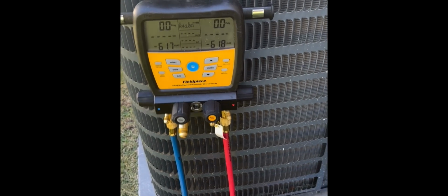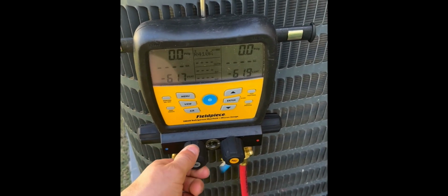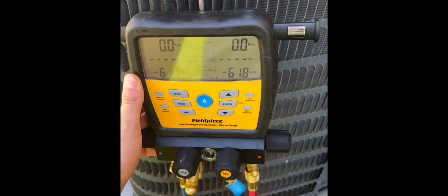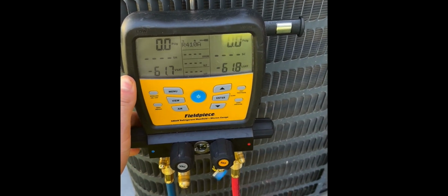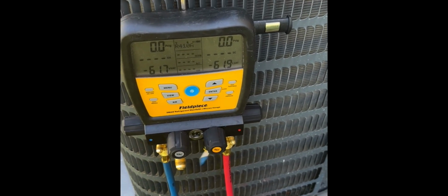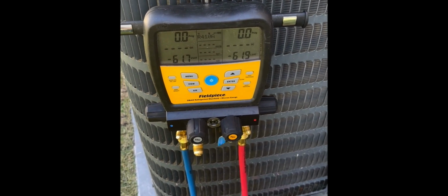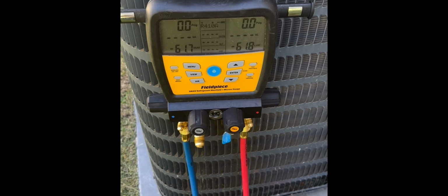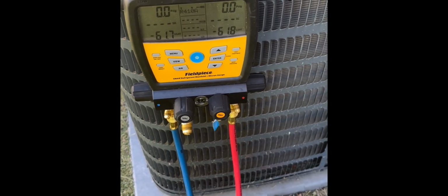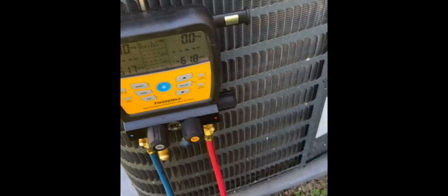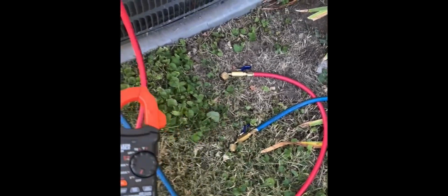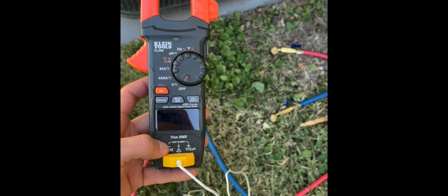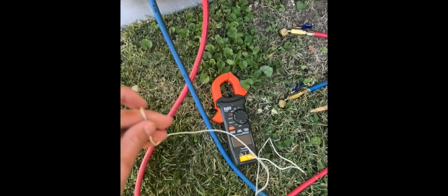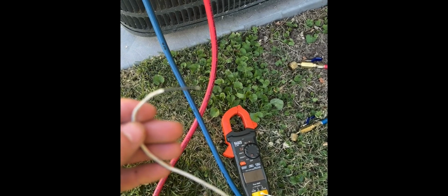So first you're going to need a set of refrigerant pressure gauges, aka manifold gauges. Now this set I have is all digital and will tell you the superheat and subcooling without you having to do any equations, but it does run a pretty high price. But you can get a normal pair for a little under $100. Second, you're going to need some kind of temperature reading device, a thermometer or anything. I have my multimeter here with a temperature probe on the end that I will tape to either one or two of the refrigerant lines down here to get an accurate temperature reading.